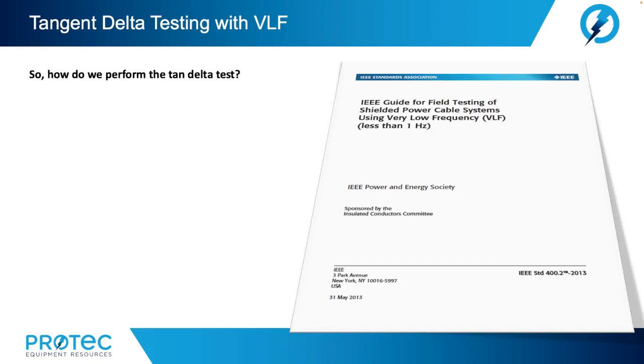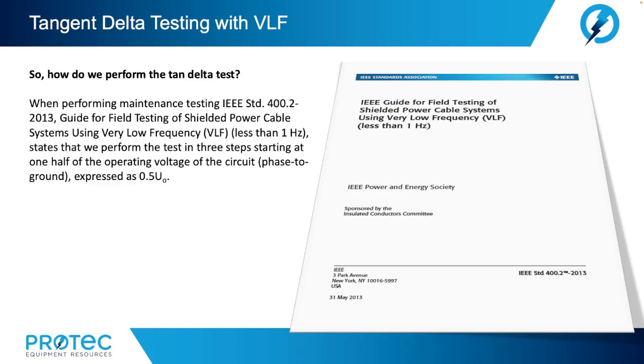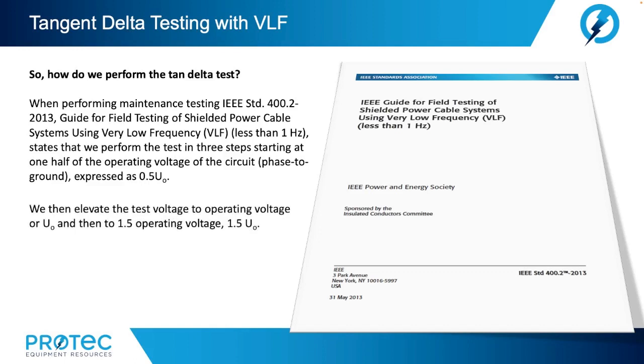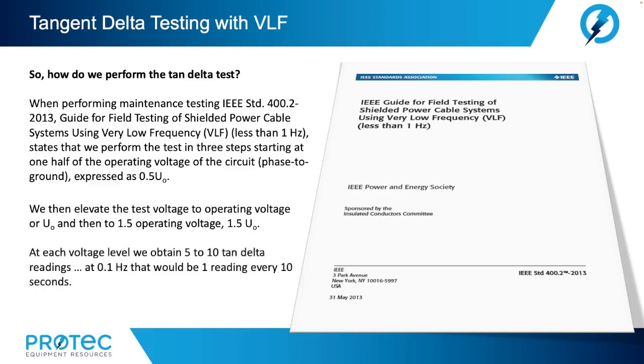So, how do we perform the tan delta test? Well, when performing maintenance testing, IEEE standard 400.2-2013, guide for field testing of shielded power cable systems using very low frequency VLF, less than 1 Hz, states that we perform the test in 3 steps, starting at 1/2 of the operating voltage of the circuit, phase to ground. This is expressed as 0.5 times U0. We then elevate the test voltage to operating voltage, or U0. And then to 1.5 times the operating voltage, or 1.5 times U0. At each voltage level, we obtain 5 to 10 tan delta readings. At 0.1 Hz, that would be one reading every 10 seconds.